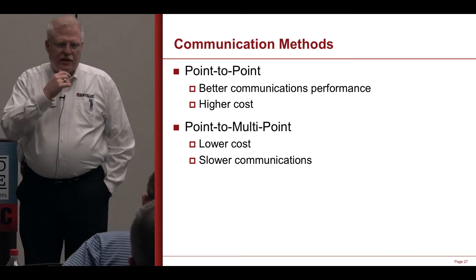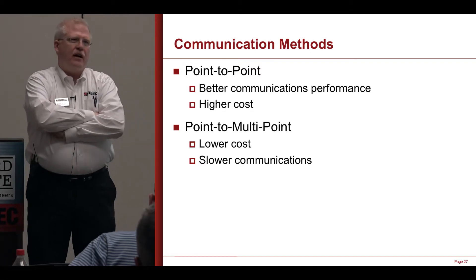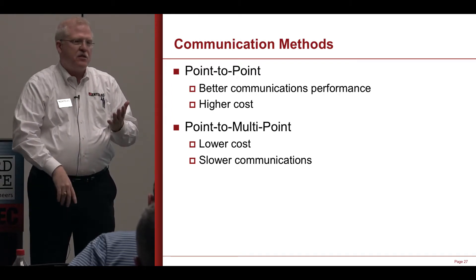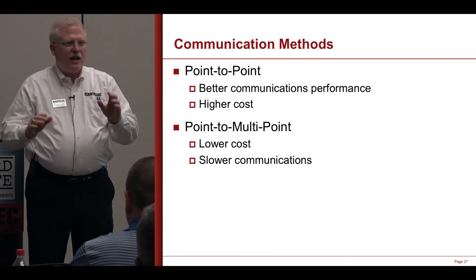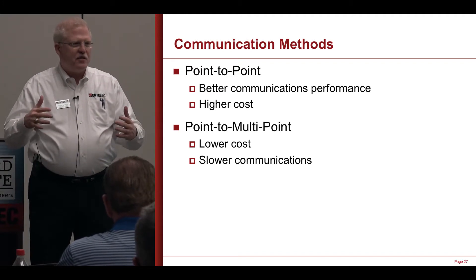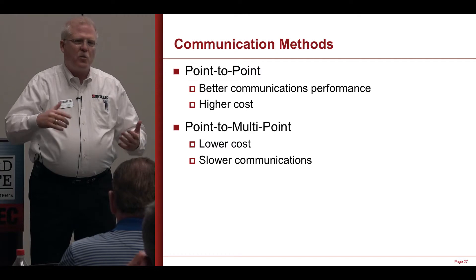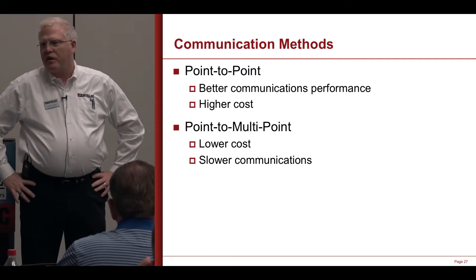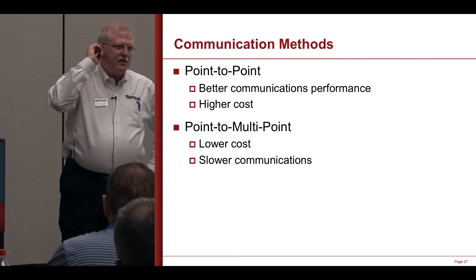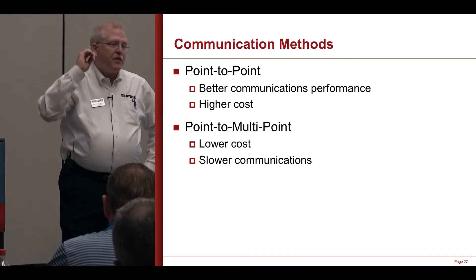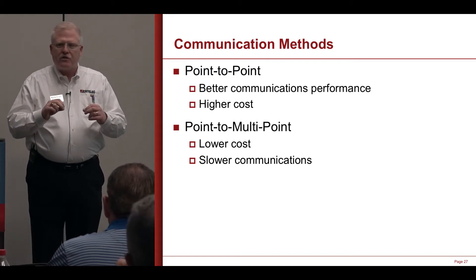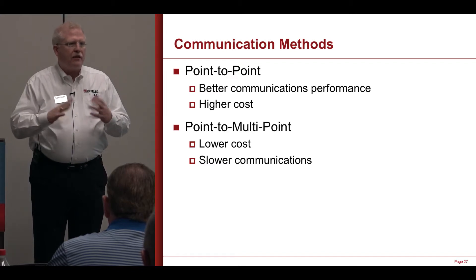What a lot of people have done — and it was especially prevalent when spread spectrum was really starting to proliferate — is that spread spectrum was inexpensive, you could put it up, and it would start communicating immediately. You just kind of put it in, point it at a tower, and you're golden. Well, over time, communications performance would go down. So what's the first thing people would do? Instead of doing three retries, I'll do five. Instead of a 60-second timeout, I'll do a 90-second timeout. So I just made everything worse. Radio networks have to be engineered, and a few bad actors have an exponential negative impact on the overall system.